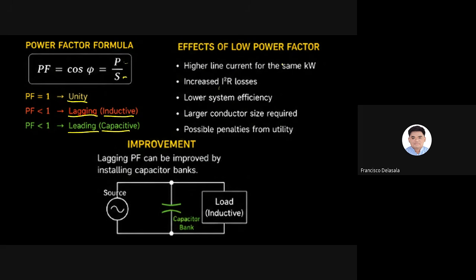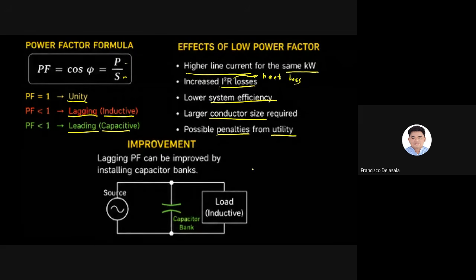So these are the effects of a low power factor: higher line current for the same kilowatt rating, meaning more losses due to heat loss, which is the I-squared-R heat loss in our conductor. Also lower system efficiency, and a larger conductor size required to compensate for the higher line current. And if it's too low, there are also possibilities of penalties from our power supplier.